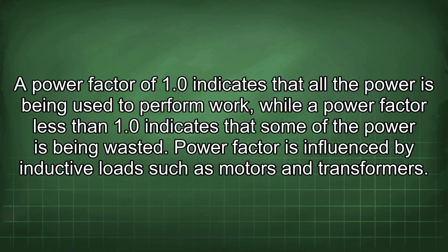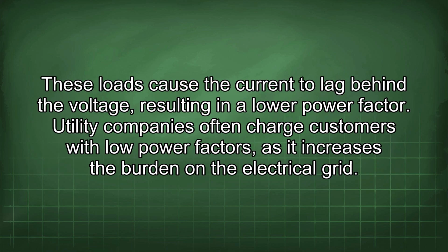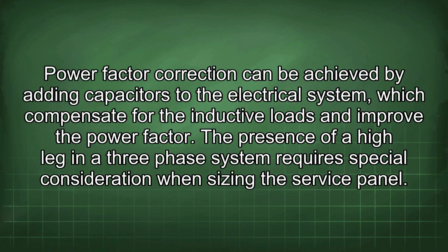Power factor is influenced by inductive loads such as motors and transformers. These loads cause the current to lag behind the voltage, resulting in a low power factor. Utility companies often charge customers with low power factors, as it increases the burden on the electrical grid.